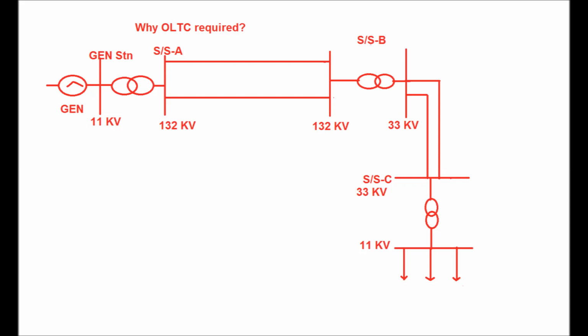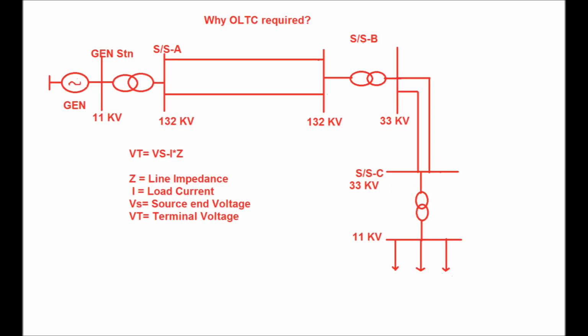In the distribution end substation, again the voltage is stepped down by means of a 33 by 11 kV transformer, and different 11 kV feeders are taken to the consumer end to supply either direct 11 kV consumers or domestic supplies through the pole mounted transformer. So this is how the generated power is transmitted from the generating substation to the 11 kV distribution feeder and again to the consumer end. Now, why is the OLTC, that is the on load tap changer, required?